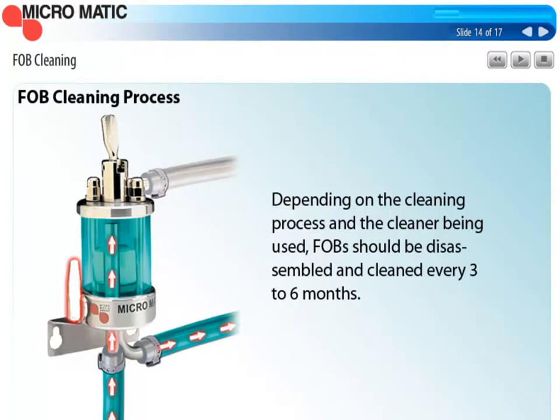When FOBs are present, there's a process that needs to be followed when you're cleaning the beer system. Make sure the FOBs are in the bypass mode. Then when the cleaning solution is circulating in the beer line, go back to the cooler and vent the FOB. That will allow it to fill completely with cleaning solution. It's also important that the FOBs be disassembled every 3 to 6 months for thorough cleaning.